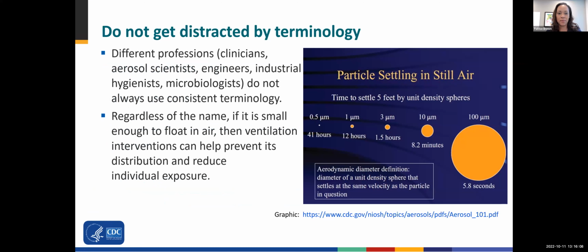All right. So the first thing I want to say, and perhaps the most important, is do not get distracted by terminology. There are a lot of different professions that are talking about this issue of infectious aerosols or COVID aerosols, and we don't always use the same terminology. So aerosol scientists, engineers, industrial hygienists, whether we're talking about aerosols, particles, or droplets, the bottom line is if it's small enough to float in the air for any reasonable amount of time, then it's going to be impacted by the airflow while it's in the air.